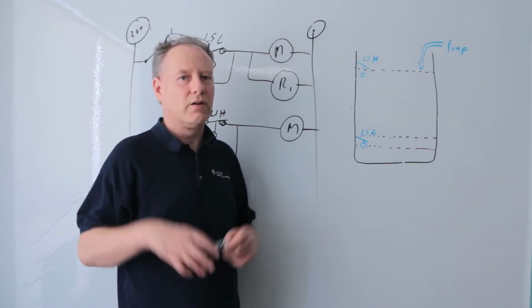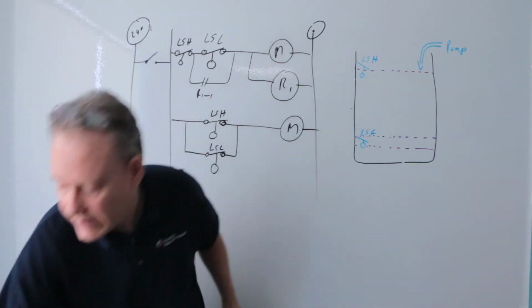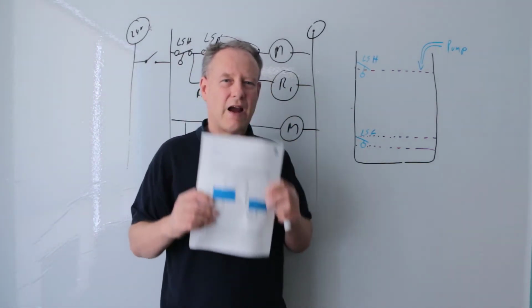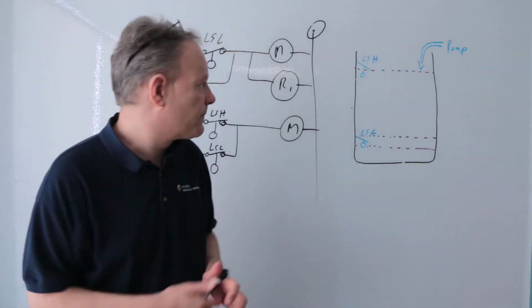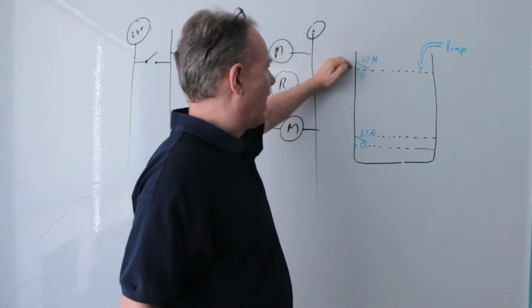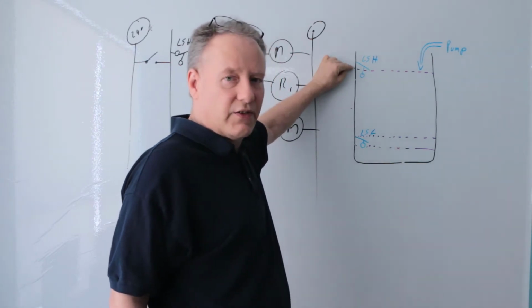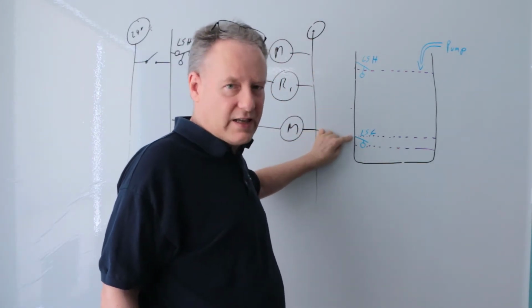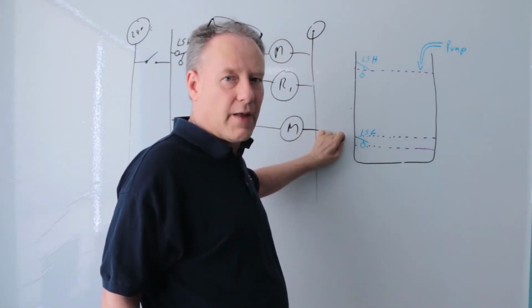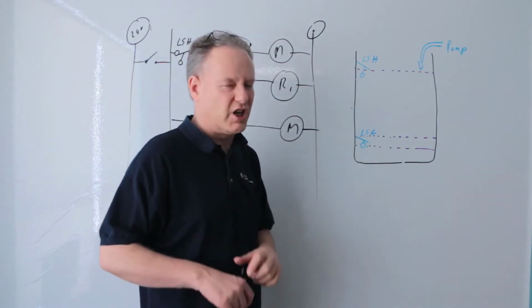It kind of goes along a little bit more than that, because the description in here, which is a great description, I love this comment here. It's about an error. And the error is this. If this guy here shows that the tank is full, and that shows the tank is empty, then there's an error. And that error's got to shut the system down. It's got to shut it down.